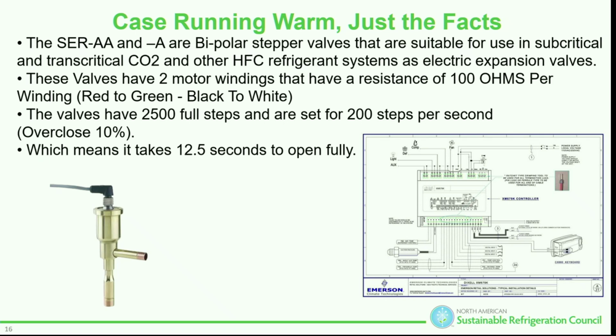One other thing I do want to mention about this, bless you, the SER-AA is the smallest valve that Sporlan makes. And a lot of times on Hussmann cases and Hill Phoenix OWIZ cases, that BTU is like 2,900 BTUs or 2,600, something a minute. If you take that CO2 valve and you run it through the mobile app to try to figure out the sizing of that valve, that expansion valve might actually come out at like a ton. So sometimes if you see valves prematurely fail, what it takes is not messing with the steps, but messing with the valve percentage. A lot of times you'll see a valve go 0 to 100, 0 to 100. It's just wearing out that valve trying to modulate superheat.